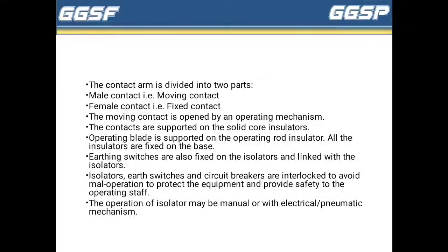It should be noted that the earthing switch, isolators and circuit breakers are interlocked with each other to ensure safety of equipment as well as the operating staff. The isolator may be operated manually or with the help of electrical or pneumatic mechanism.